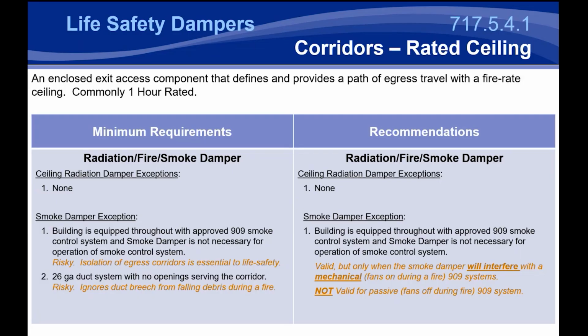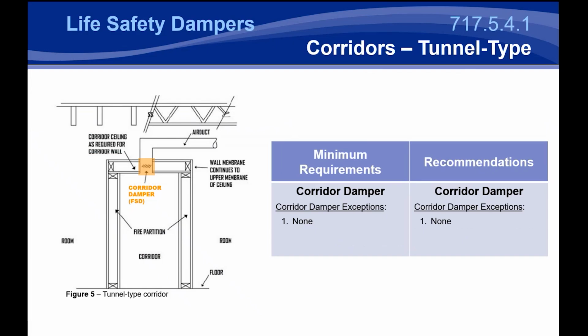Now, the sidewall penetrations are exactly the same whether you have a rated ceiling or not. So typically, I won't go through those again. But if you do have a rated ceiling, you do have to have that ceiling membrane protection. So you have to have that ceiling radiation damper for those applications. I talked a little bit in the beginning of the presentation about tunnel type corridors. Those tunnel type corridors use a portion of the continuity section of the code to be able to extend the continuity of the wall to a non-load bearing ceiling. This is very important because you have to use the same stud construction of the wall or the same concrete construction of the wall for the ceiling. Typically, this is going to be stud construction because corridor walls and corridor ceilings for tunnel type applications are typically rated for only 1 hour.